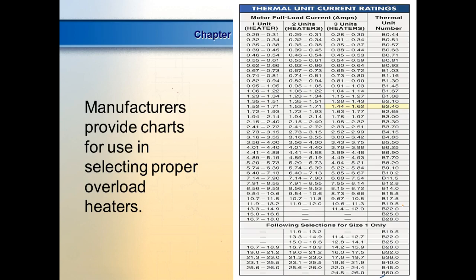Now this does not consider the thing that we call the service factor. Service factor means we can literally, legally overload that motor. Not permanently, usually for short runs. If you run it at its full service factor all the time, then the motor is going to fail sooner. It'll run okay, but it fails sooner. Just like in your car, if you run the dang thing wide open, it may not fail, but it's going to fail sooner than it would if you ran it at its normal rating.